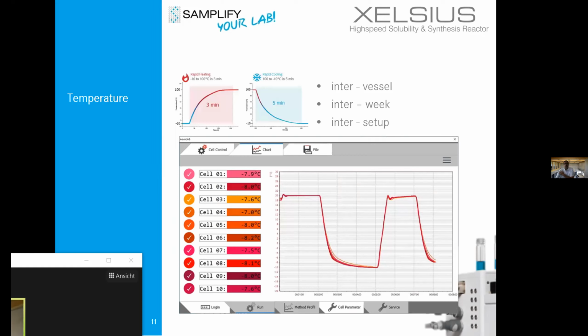So when we talk about temperature, we have here in our instrument 10 different reaction cells, and this gives an idea about the temperature, how important it is to have the same temperature management in each reaction vessel. And it's a question between the vessels, but it's also a question of time.